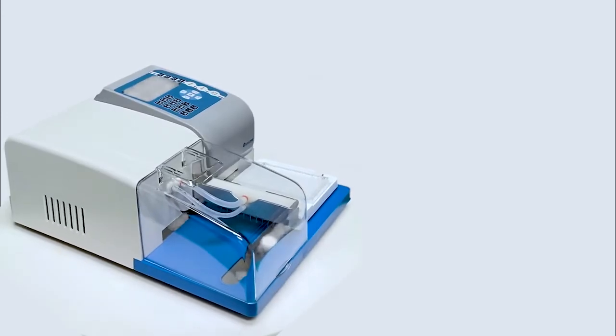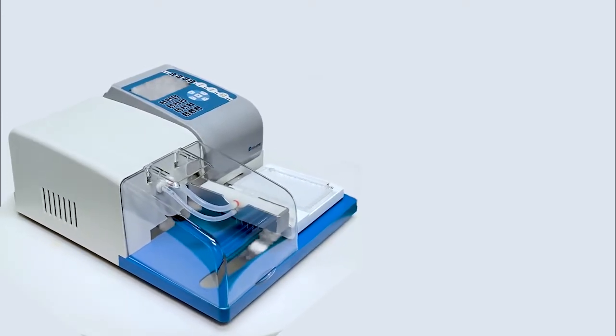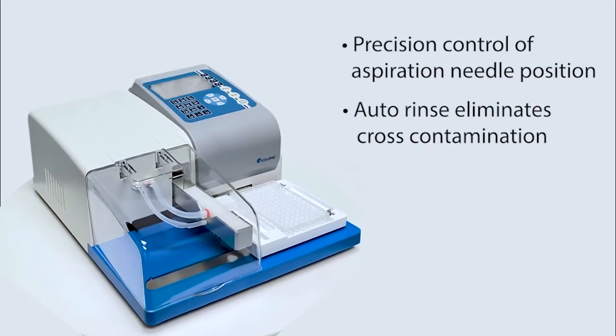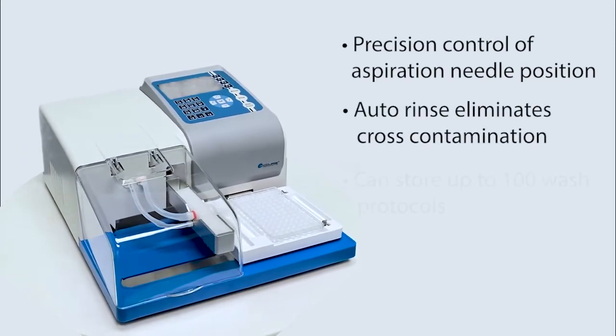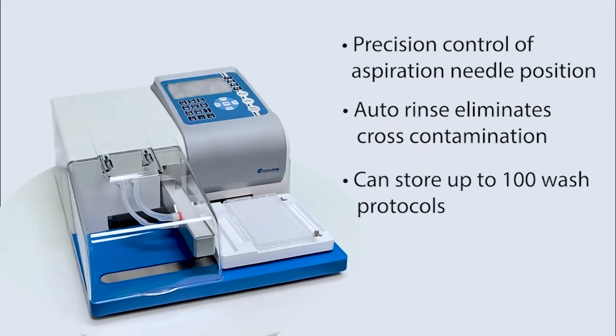Introducing the Accuris SmartWasher 96. The SmartWasher 96 is an automated microplate washing system that offers precision control of aspiration needle position, features an auto rinse function that eliminates cross-contamination, and allows editing and storing up to 100 wash protocols.